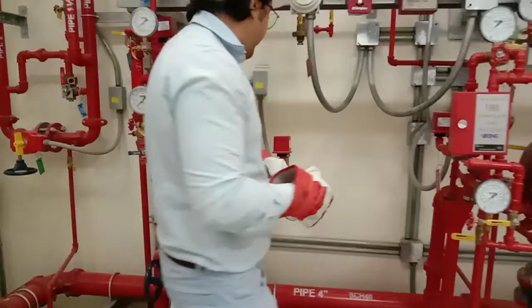the system is activated. Again, we have the PS10 Potter main supervisory switch. It will give a signal to the fire alarm panel, and the system is activated. So for the deluge valve, we have 3 gauges, right? The one at the bottom tells us about the water pressure. What is the water pressure we have from the supply line?